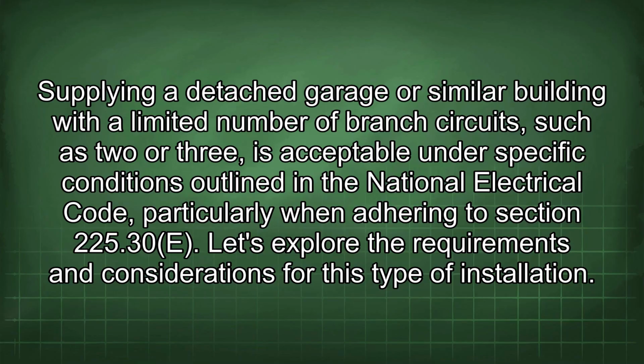Supplying a detached garage or similar building with a limited number of branch circuits, such as 2 or 3, is acceptable under specific conditions outlined in the National Electrical Code, particularly when adhering to Section 225.30(E). Let's explore the requirements and considerations for this type of installation.